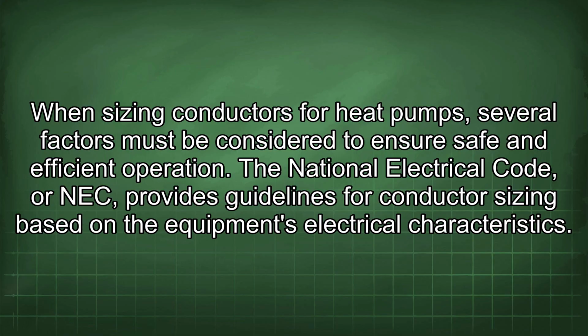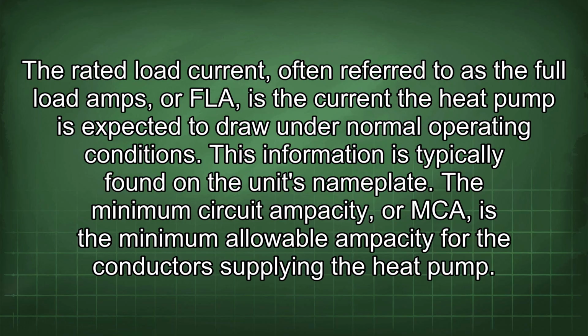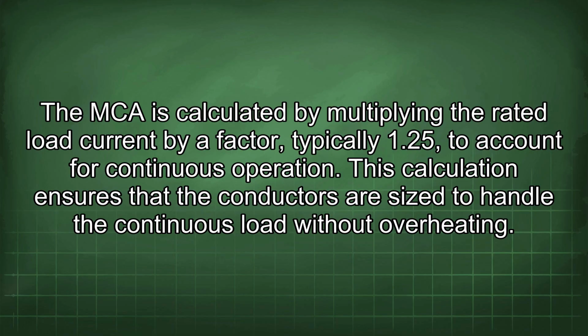The National Electrical Code, or NEC, provides guidelines for conductor sizing based on the equipment's electrical characteristics. The rated load current, often referred to as the full load amps, or FLA, is the current the heat pump is expected to draw under normal operating conditions. This information is typically found on the unit's nameplate. The minimum circuit ampacity, or MCA, is the minimum allowable ampacity for the conductors supplying the heat pump. The MCA is calculated by multiplying the rated load current by a factor, typically 1.25, to account for continuous operation. This calculation ensures that the conductors are sized to handle the continuous load without overheating.